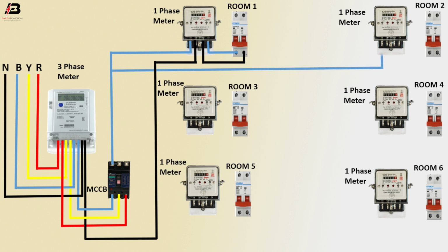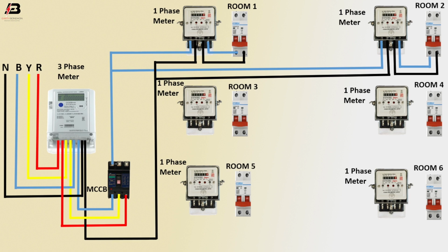Phase connection to the room 2 energy meter. Neutral connection to the room 2 energy meter. Neutral connection from the room 2 energy meter to the room 2 circuit breaker, and phase connection from the energy meter to the circuit breaker.